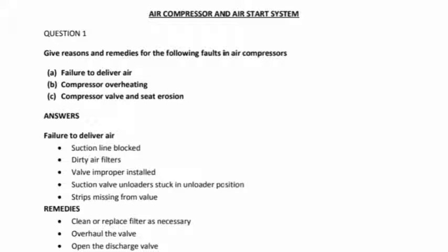For failure to deliver air, number 1, the suction line may be blocked. Number 2, dirty air filters. Number 3, valve improperly installed. Number 4, suction valve unloader stuck in unload position. And the final one, strip missing from valve.